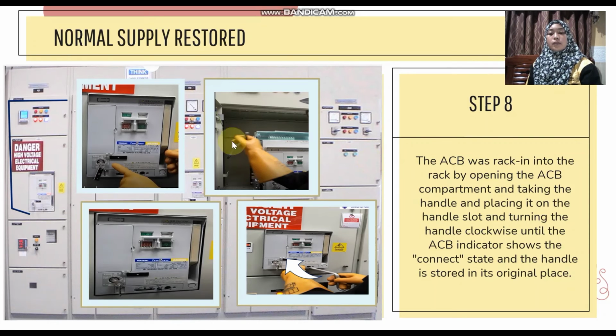Now is step number 8, where we want to rack in the circuit breaker. The first step is we need to find the handle. The handle is basically in the compartment. After that, we plug it into the slot of the handle, then turn it clockwise until the indicator shows connect. After that, the handle is stored in its original place.